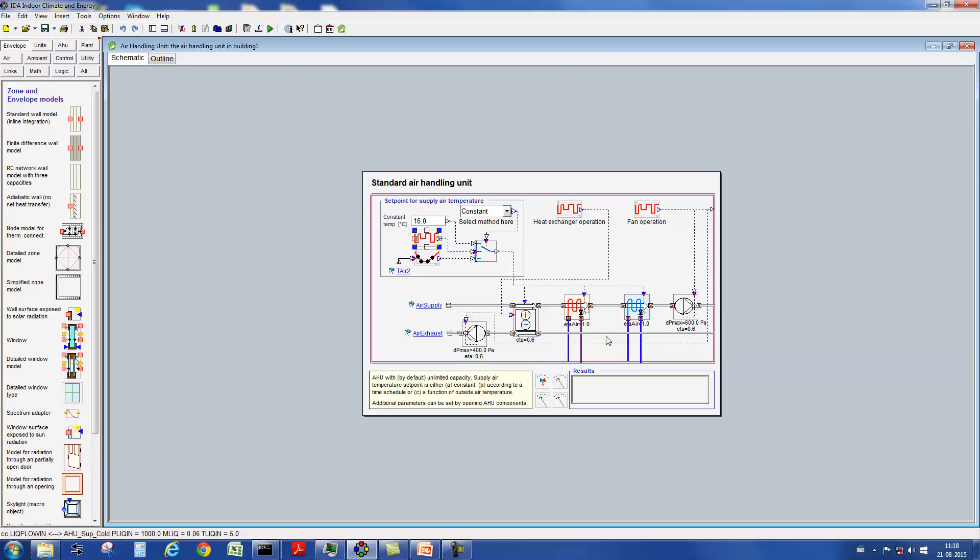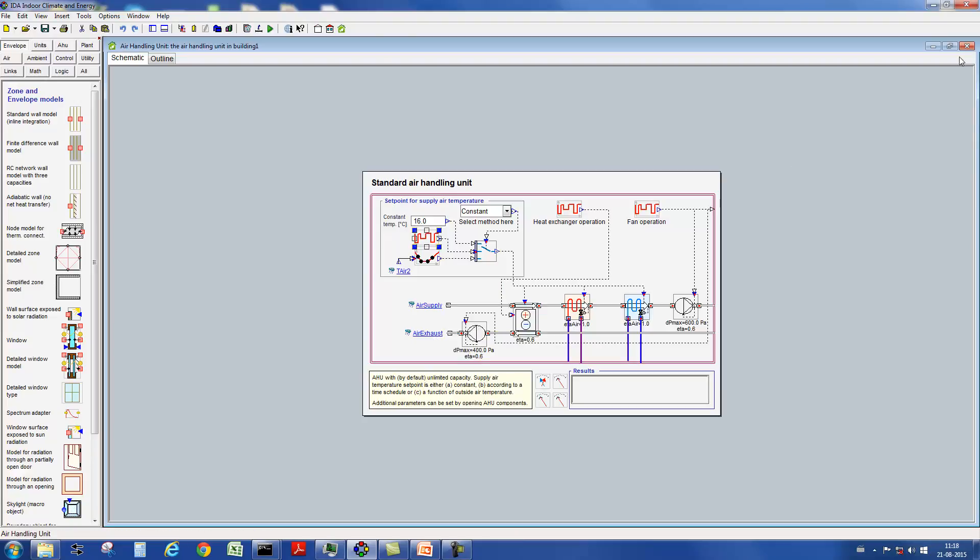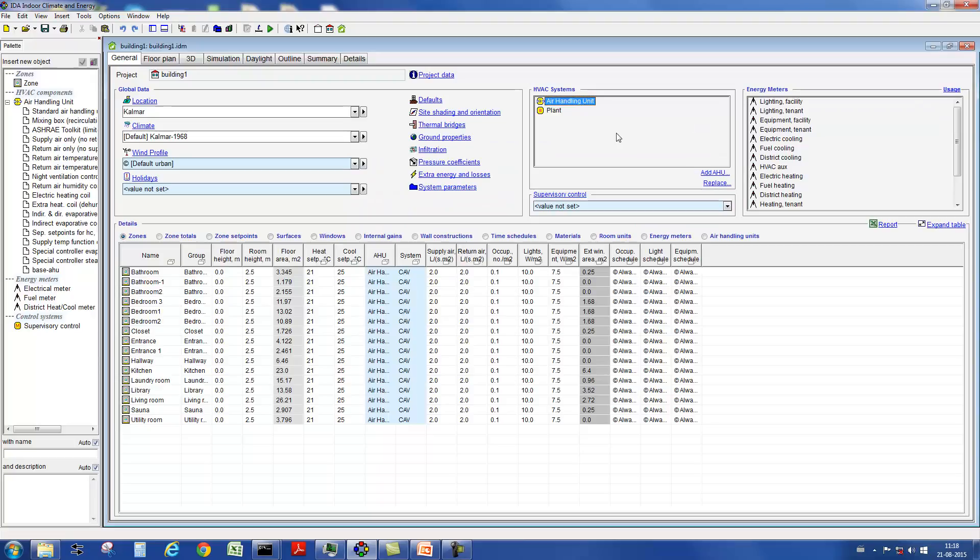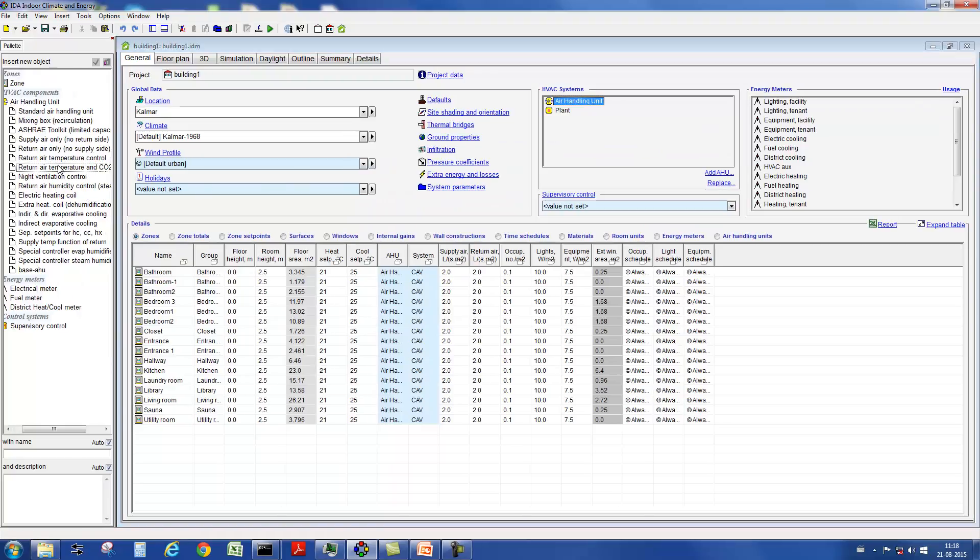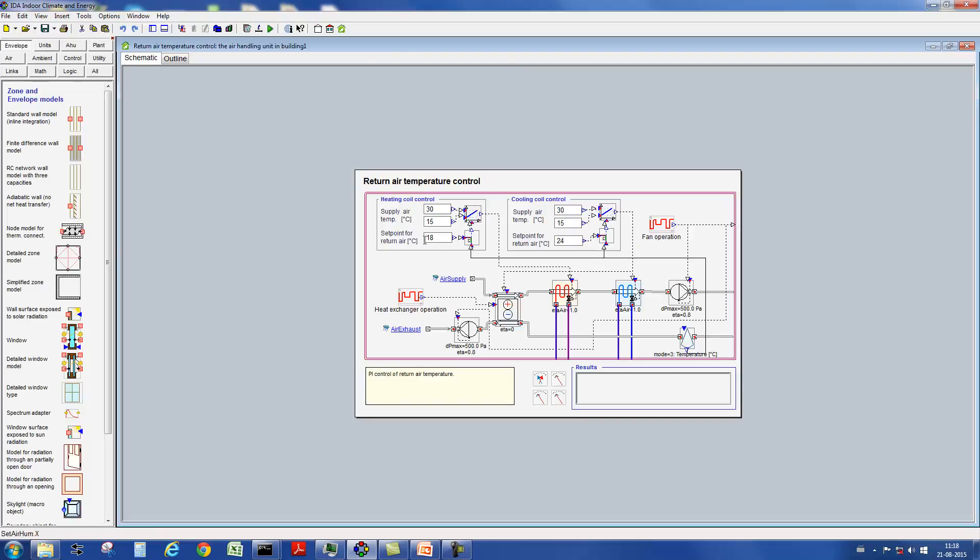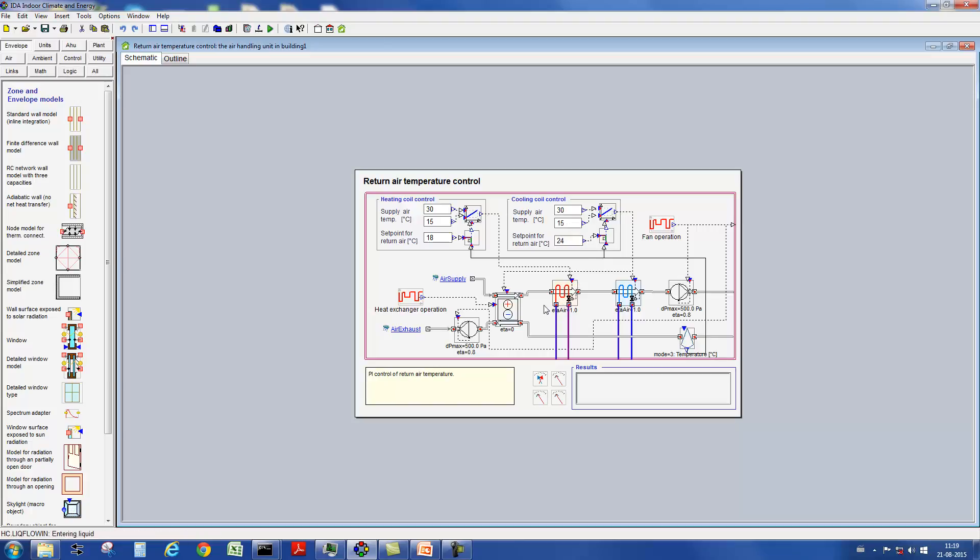This is the return air flow. IDA ICE has a series of other pre-specified air handling units, all of which are included into the model through a very easy drag and drop system. For instance, an air handling unit with a control of the supply air temperature as a function of the return air temperature from the zones. Set points are specified for the return air stream and the possible temperature variation of the supply air stream.